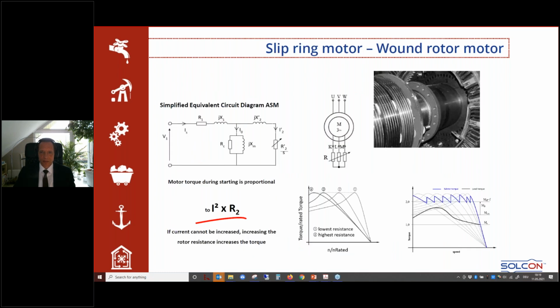Then I mentioned the slip ring motor. Here we have to do a little bit of an excursion into the electrical theory. What you see here is a simplified equivalent circuit diagram of the asynchronous machine. What is important to remember is that the motor torque during starting is proportional to I square rotor resistance. So if you do not have the possibility to increase the motor starting current due to the network, you can increase the rotor resistance by connecting external resistors via slip rings to the motor.